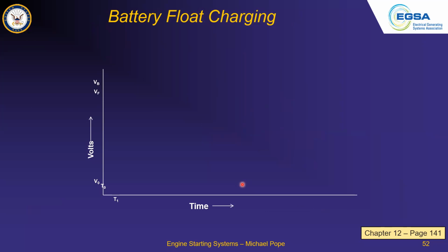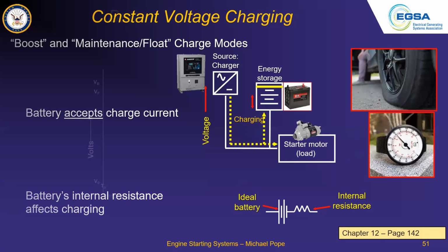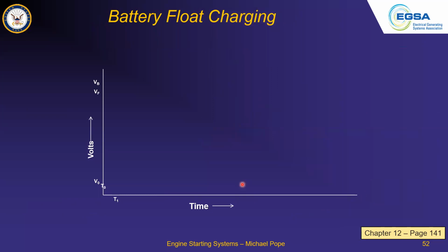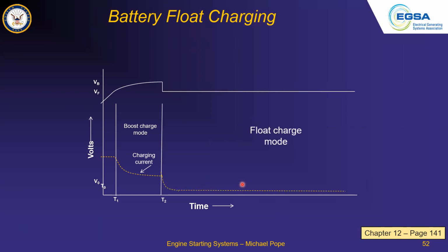So with charging the battery, let's say we've had a starting event, so the voltage on the battery has gone down. The battery charger will sense that, and it's going to do a boost charge. It's going to see that there is quite a lot of voltage that is needed, and it's going to supply that. That's what the battery charger does. It senses the voltage, compensates for it, and continues the voltage until the charge in the battery reaches a certain level. Then it's going to go from the boost charge to the float charge. We don't want to overcharge that battery because that's going to cause it to get hot, and that will shorten its life.